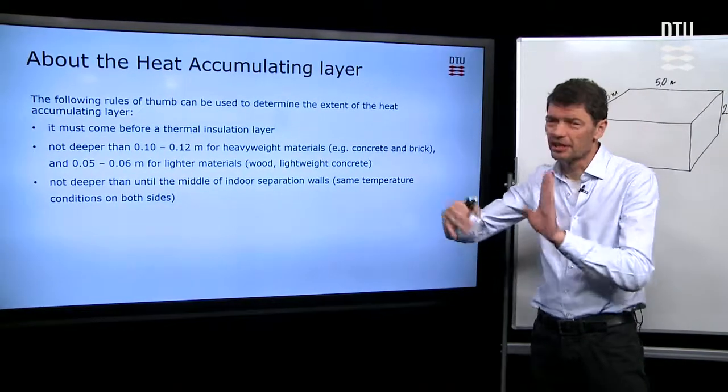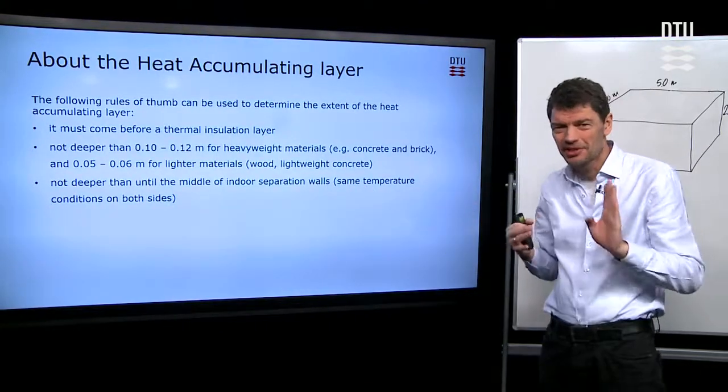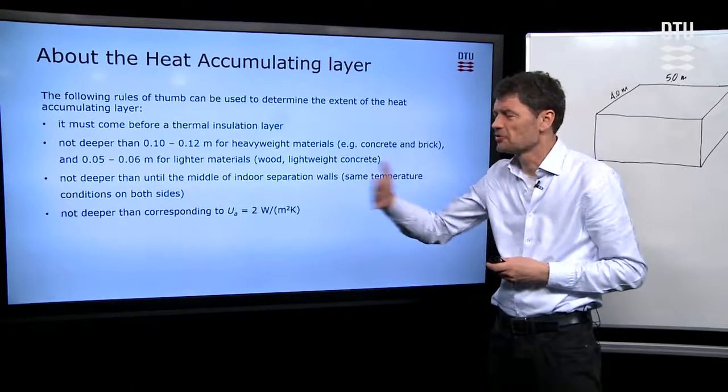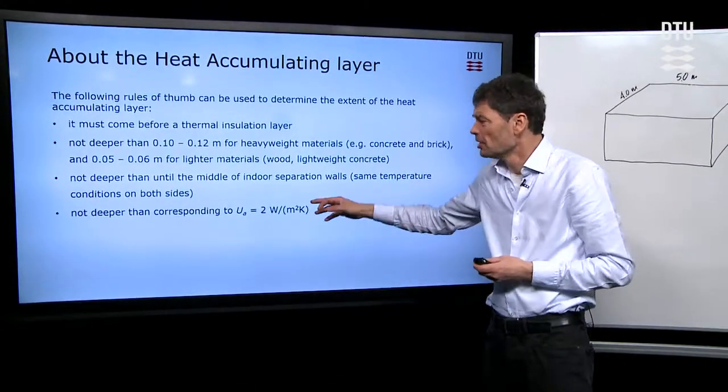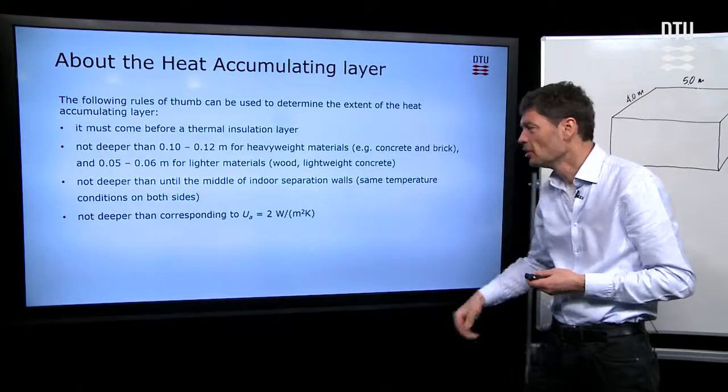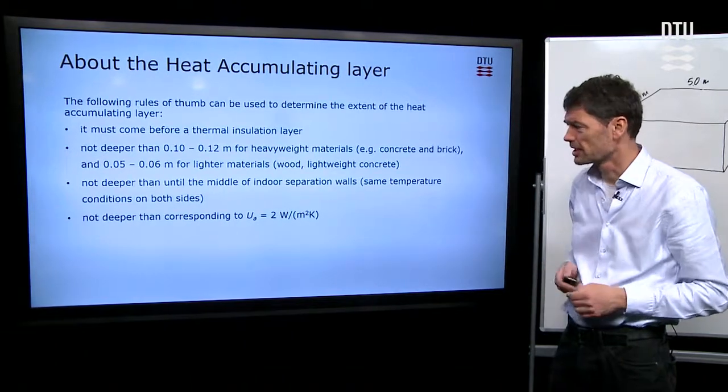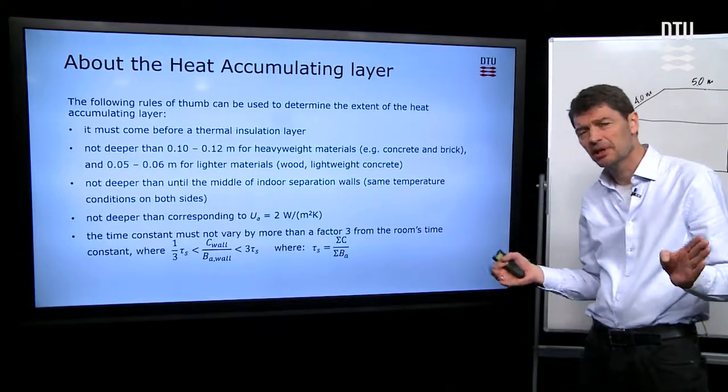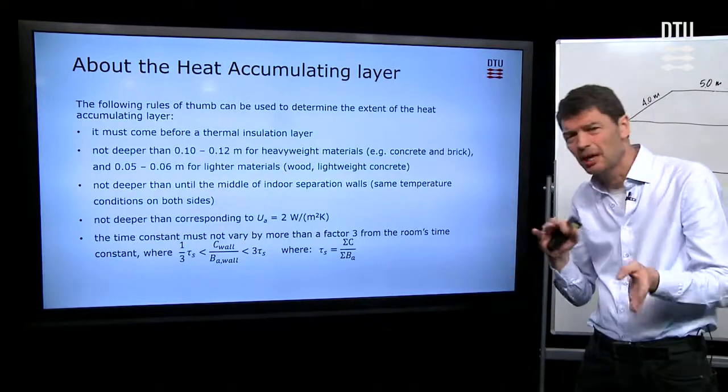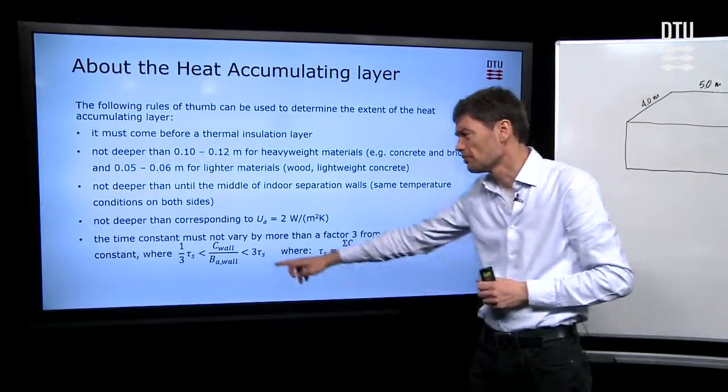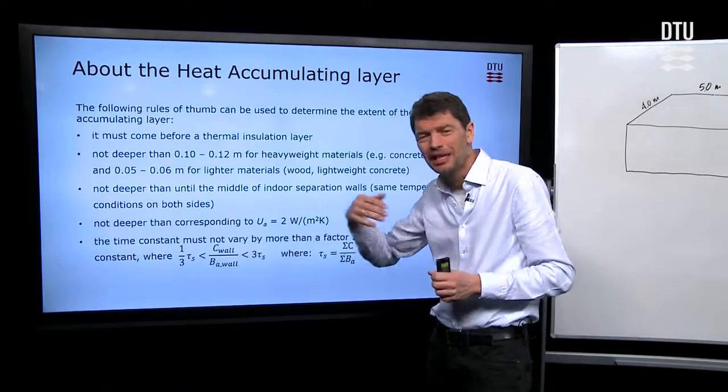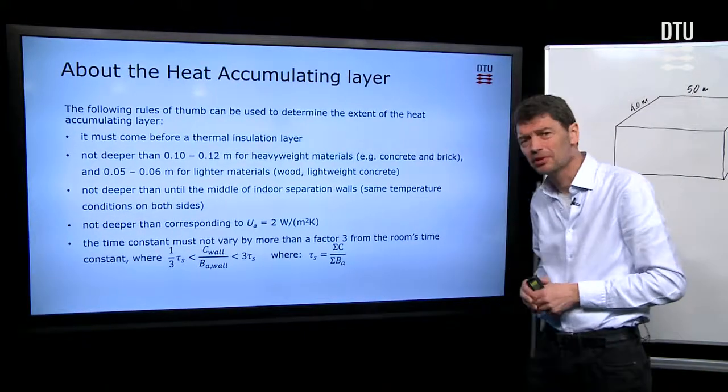If you have things that are symmetric, so you have a similar room on two sides of an interior wall, then you should of course consider only until the middle of the wall. Also, if the heat transmission into those layers in the wall is not so good, then we should consider only until we have a heat transmission coefficient into the layer which has to be larger than two watts per square meter Kelvin. And also, considering the time constant, since we have different components contributing to giving heat capacity to the room, they should more or less be of similar time constant, each of the individual components. For each wall or material, you can calculate its contribution to the time constant. And this should be not more than a factor, say three, less or more than the average or the whole time constant for the whole room.